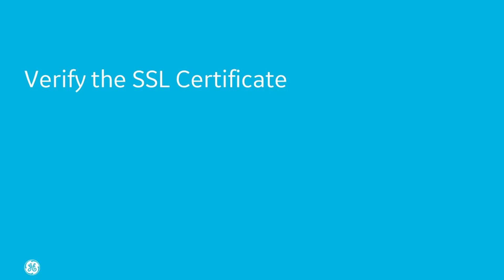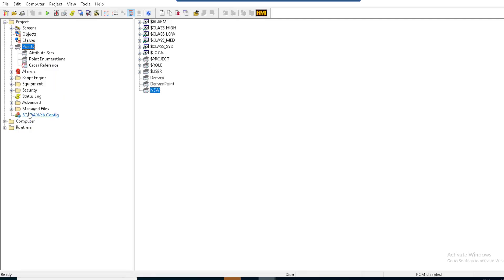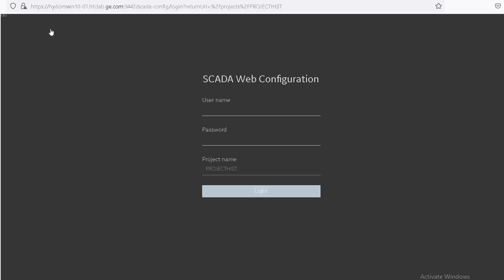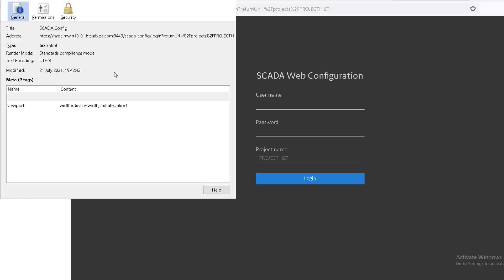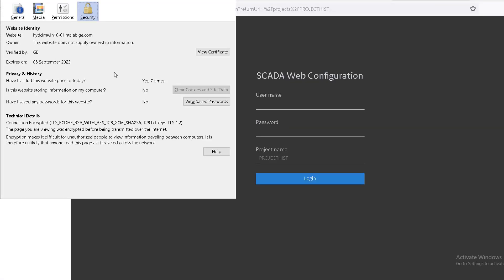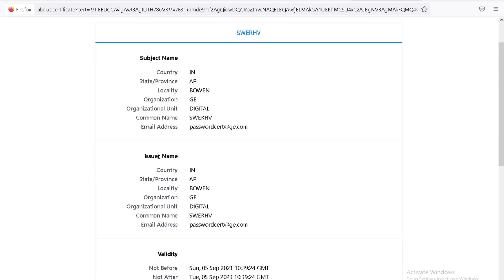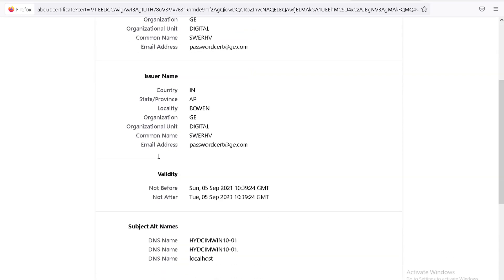To verify the SSL certificate, launch SCADA Web Config from Workbench. Click the lock icon and view the certificate. These are the details that I entered by generating the CSR. This confirms that the SSL certificate is updated successfully. This is the validity of the certificate. Congratulations, your SCADA Web Config sessions are now secure.